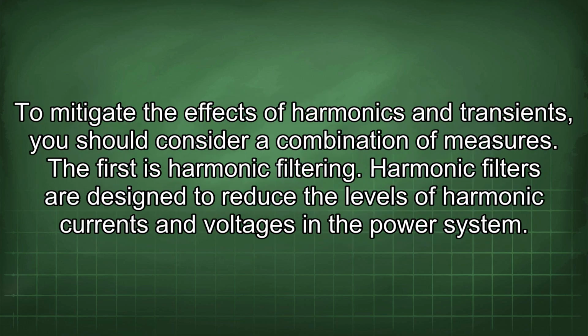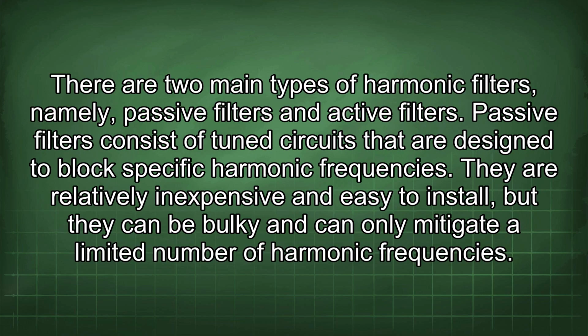To mitigate the effects of harmonics and transients, you should consider a combination of measures. The first is harmonic filtering. Harmonic filters are designed to reduce the levels of harmonic currents and voltages in the power system. There are two main types of harmonic filters, namely passive filters and active filters. Passive filters consist of tuned circuits that are designed to block specific harmonic frequencies.